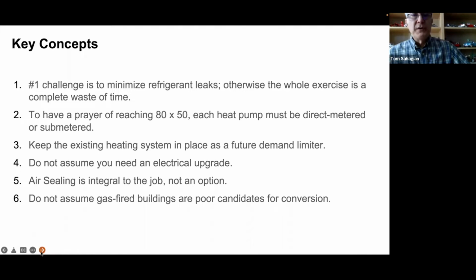The main things we learned, and this is by no means an exhaustive list, is that the biggest challenge on projects like this is to minimize refrigerant leaks. The reason for that is that the refrigerant used in these systems has a very high global warming potential, 2,200 times that of CO2. So if the system is not set up properly and carefully, and the refrigerant leaks out, you might get a lot of energy savings, but then the greenhouse gas savings you were hoping for just literally evaporate into thin air. So it's very important to make sure the installation is done properly.